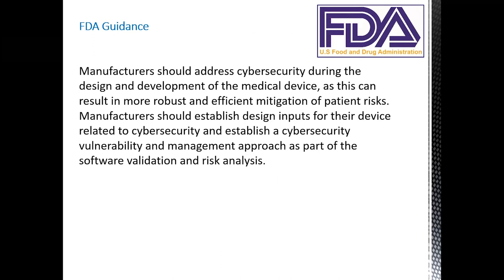Manufacturers should establish design inputs for the device related to cybersecurity and establish a cybersecurity vulnerability and management approach as part of the software validation and risk analysis. Again, it's important that cybersecurity or information security is addressed during the design and development of the device. It's not something that can be bolted on at the end.